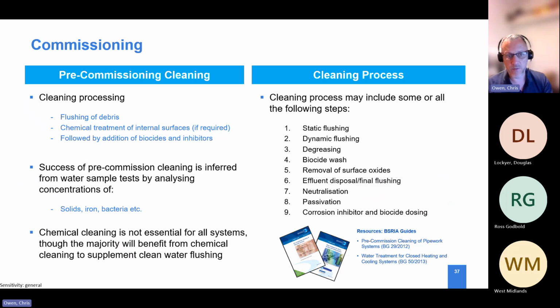We like both, because commissioning with chemicals means that you're cleaning the inside of the tube. If you're using biocide washes or inhibitors within there, you're adding chemicals which are going to mitigate the risk of bacteria, which can result in corrosion. However, if you've got real-time monitoring, you're collecting data which allows you to ascertain whether something has changed in your system, and it might not be down to pipework, it could be down to something else which has either failed or some other retrofit work which has taken place, which has added more oxygen into the system. So a mixture of both might be quite beneficial.